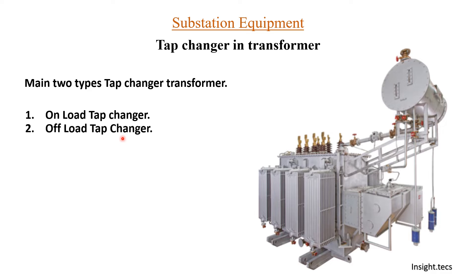Offload tap changers are generally seen in transformers having smaller capacity — about 100 kVA, 200 kVA, and up to 500 kVA. But these transformers have to be in such a way that they have the possibility of turning off easily. This kind of offload tap changer cannot be provided to any industry which is running for 24 hours, as any disturbance for changing of tap will hamper the industry power supply. So in cases where it is okay to turn off the transformer for some time and do the tap changing process, we use offload tap changers. Otherwise, for higher capacity transformers and transformers which cannot be turned off easily, we always use onload tap changers.